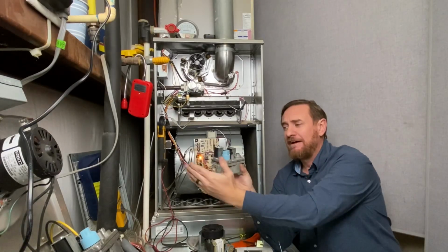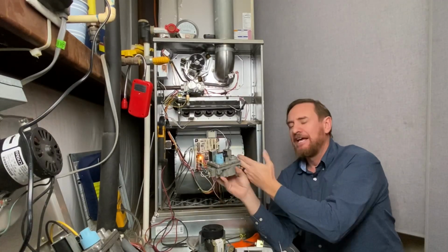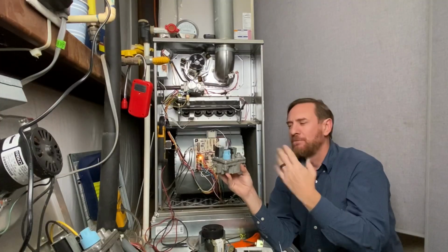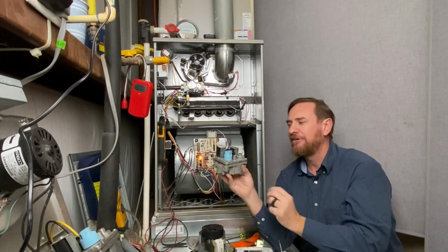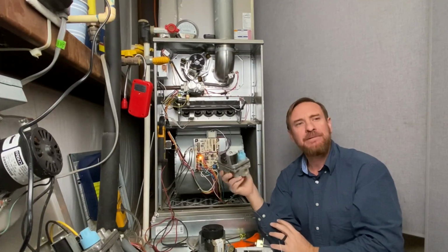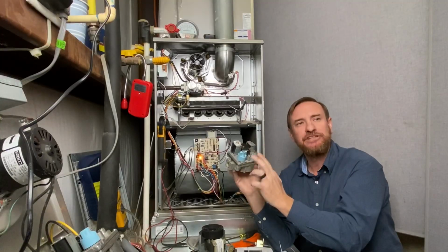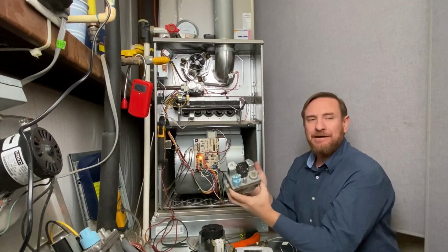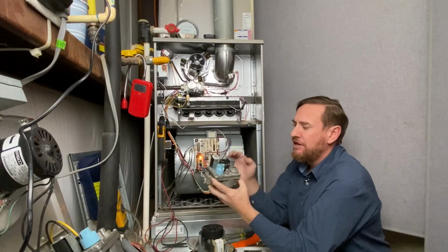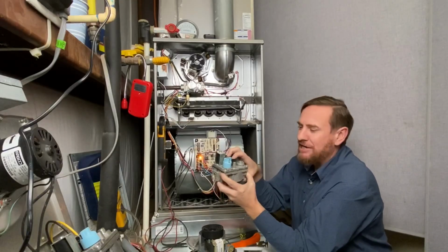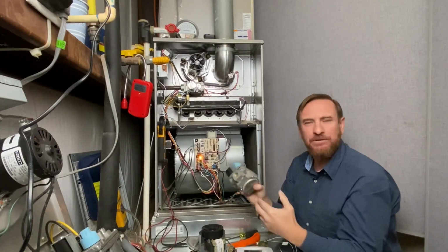So you've got to think, do I have the proper gas pressure coming in and the proper gas pressure coming out? We'll do gas pressure and how to in a separate video, but this is a combination gas valve. So you've got to diagnose it as 2 parts. So you want to see, am I getting 24 volts to this gas valve? Hook your meter up with your wires, and you have to wait for the proper sequence of operation.